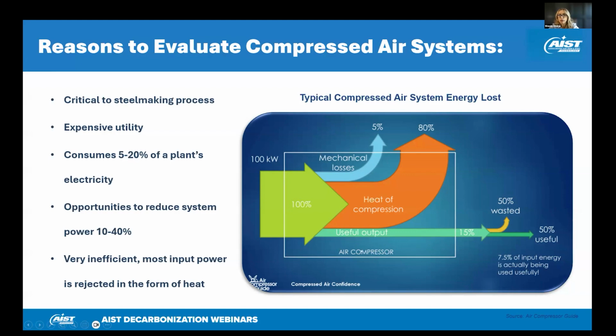Compressed air is critical to the steelmaking process in many ways. It's also a very expensive utility. The electric drive motors on compressors consume up to 20% of the plant's electricity. There's many opportunities to reduce the system power by up to 40%. In addition to that, there's opportunities to reduce the total cost of ownership by up to 50%.